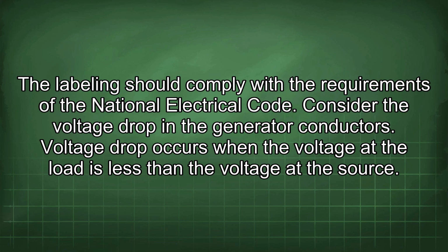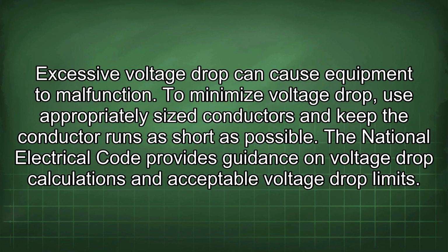Consider the voltage drop in the generator conductors. Voltage drop occurs when the voltage at the load is less than the voltage at the source. Excessive voltage drop can cause equipment to malfunction. To minimize voltage drop, use appropriately sized conductors and keep the conductor runs as short as possible. The National Electrical Code provides guidance on voltage drop calculations and acceptable voltage drop limits.